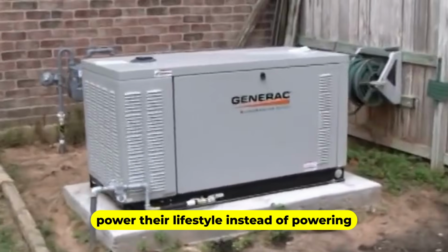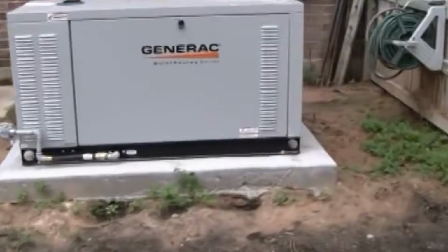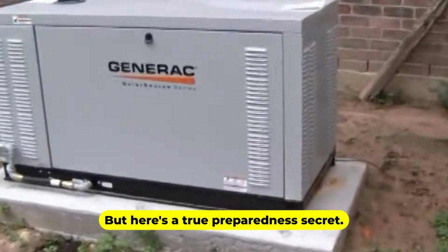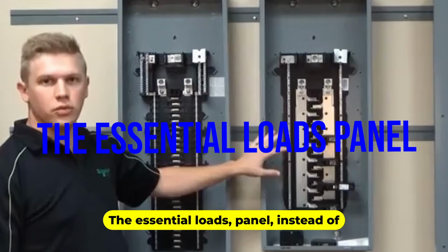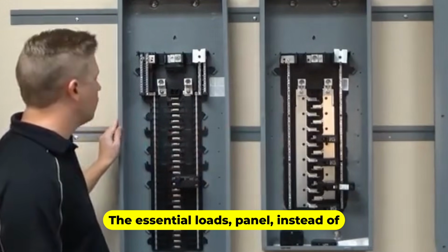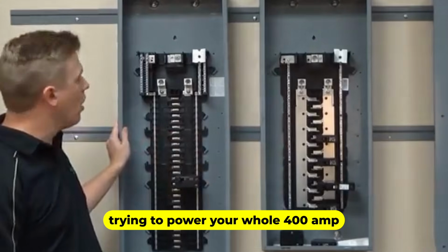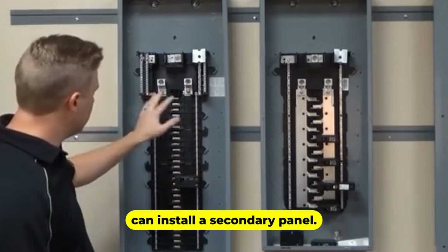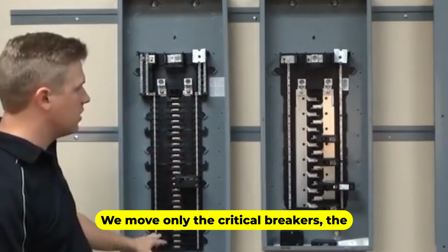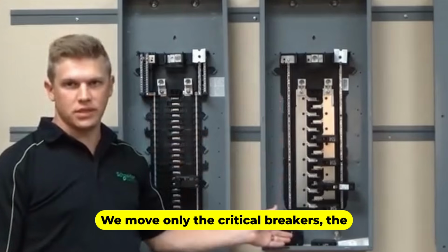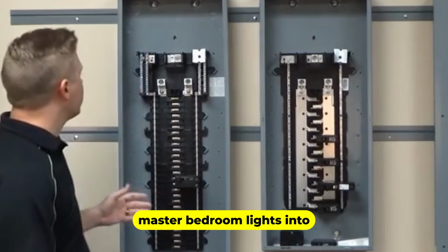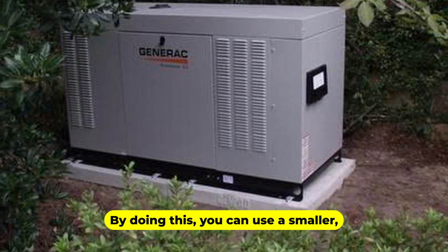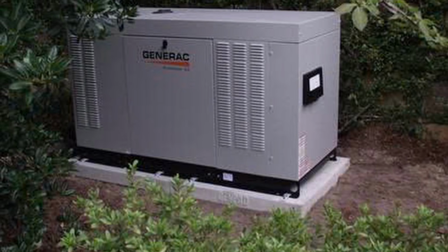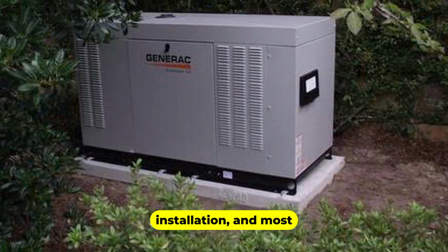But here's the true preparedness secret. The essential loads panel. Instead of trying to power your whole 400 amp service, an electrician can install a secondary panel. We move only the critical breakers, the fridge, the heater, the master bedroom lights into this panel. By doing this, you can use a smaller, more efficient generator. This saves you money on the unit, the installation, and most importantly, the fuel consumption.